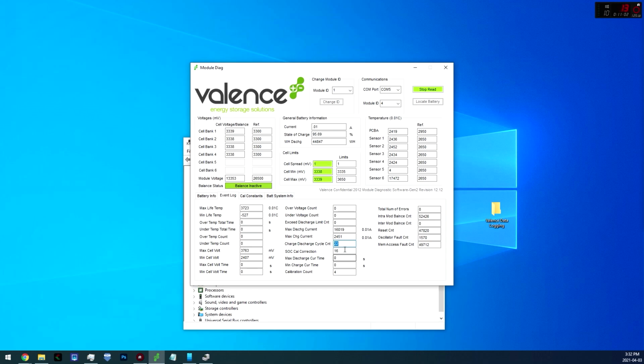So SOC cal correction, so state of charge cal correction. So Valence has the state of charge meter for the batteries, so it will show you the percentage charge it is. So as the batteries get older, the internal resistances change. So a state of charge meter will become inaccurate as the battery gets older. So this number is to compensate for age, and it either adds or subtracts this number to compensate for the age and give you a proper state of charge measurement.